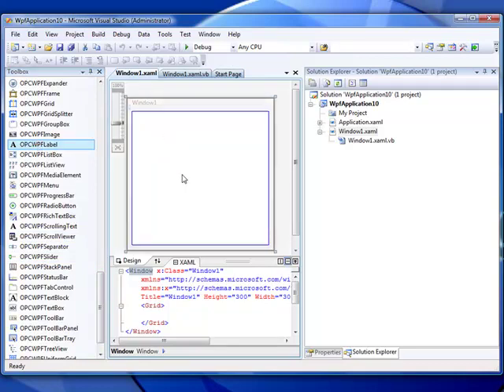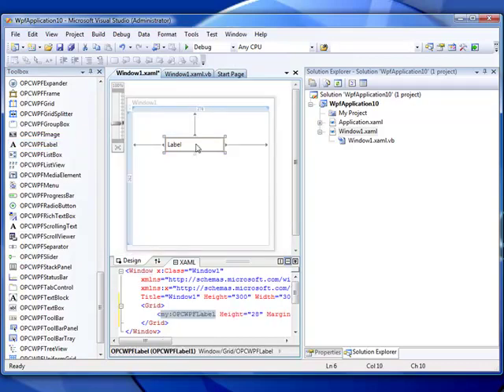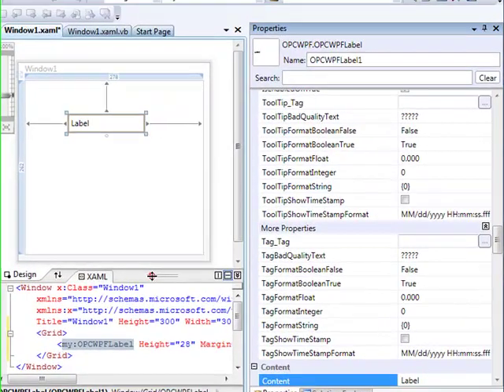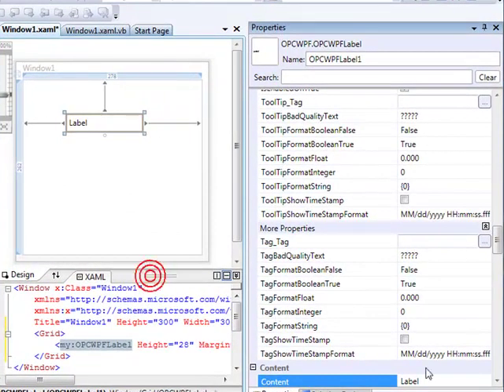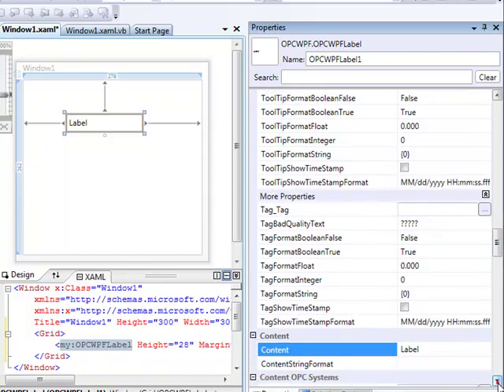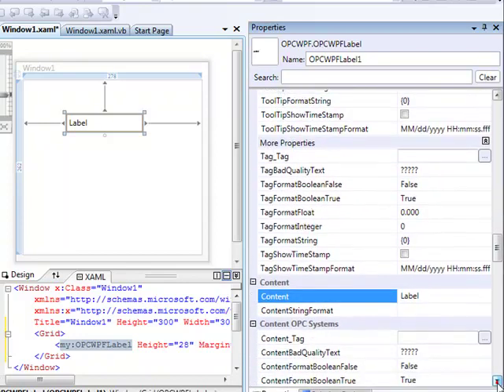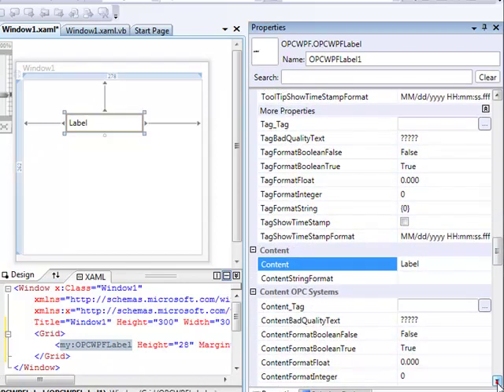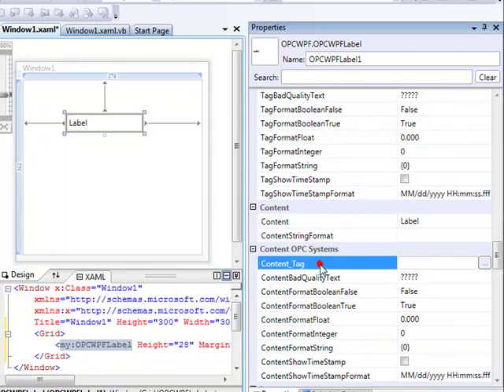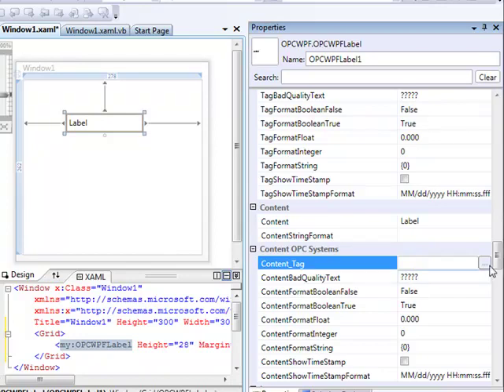Let's drop in the label control. With the label control, let's now right click on it to select Properties. You can also hit the F4 key to bring up the property inspector. The most common property of a label control is the content that is displayed within the control itself. Just below that, we will see another property group called Content OPC Systems. There is a property which is content underscore tag. For each of the properties that you would want to automatically update, there is a corresponding tag property assignment to allow you to define it to an opcsystems.net tag or a direct OPC item from an OPC server.